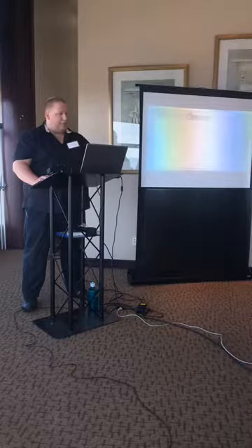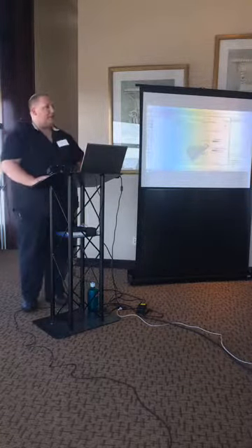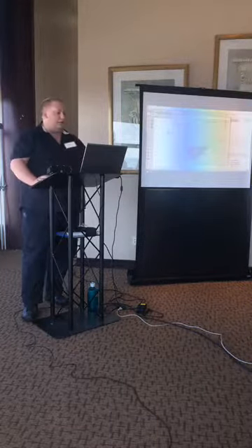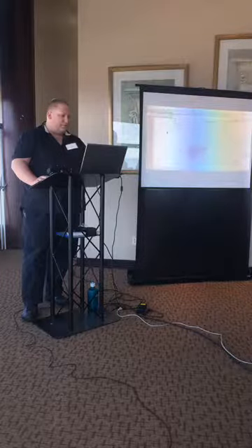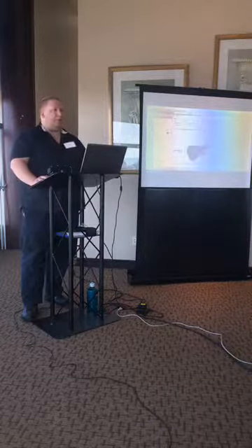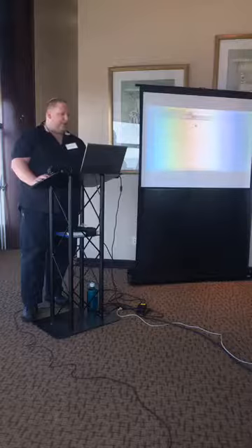I'm resetting all the parameters to be default Fathom. Okay, the next thing I'm going to do is define the discharge reservoir. This is going to be at a 200-foot elevation. So 200 feet, and we'll just keep the pipe at the top of the tank at that point there. Click OK. And then finally, we need to specify the pump.